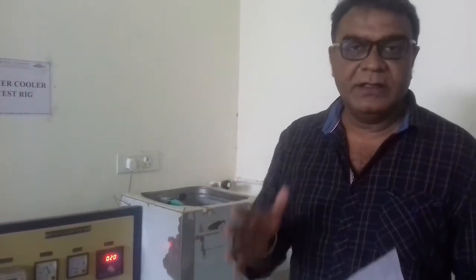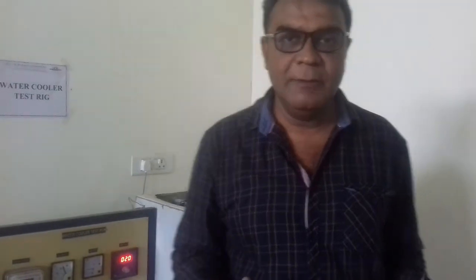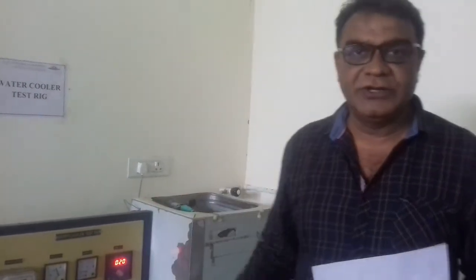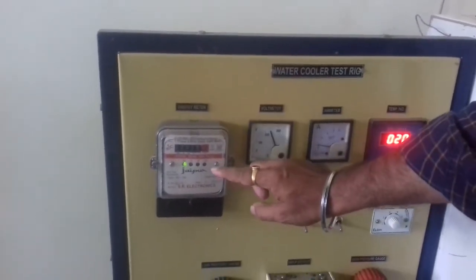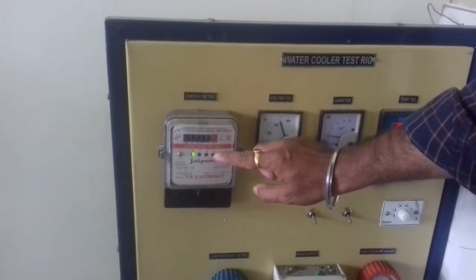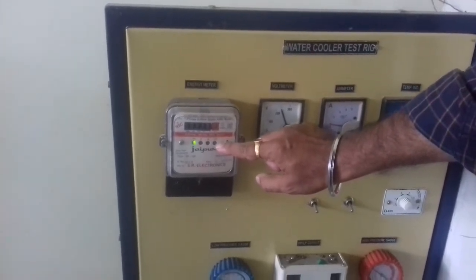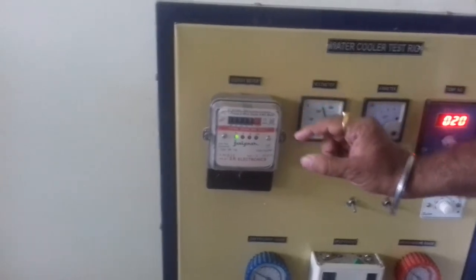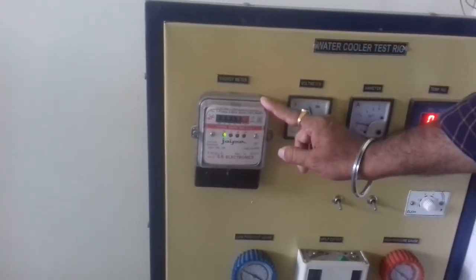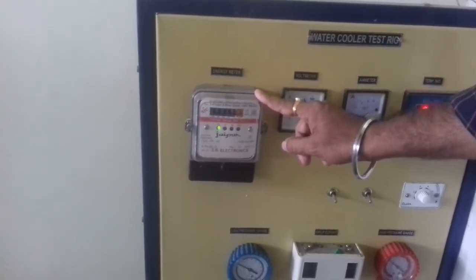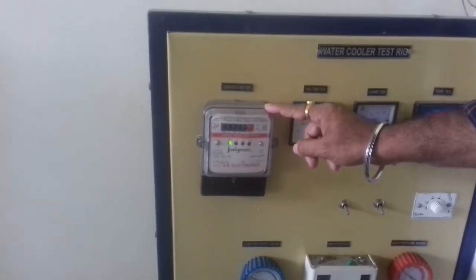By finding from the pressure-enthalpy chart we can find out the enthalpy, and from enthalpy we can calculate the COP. From this we can find out the theoretical COP. Now for the actual COP, we have to measure the time for 10 blinks. Here you can see the light which is blinking — for 10 blinks we have to measure the time. From this we can find out the actual work supplied to the compressor.